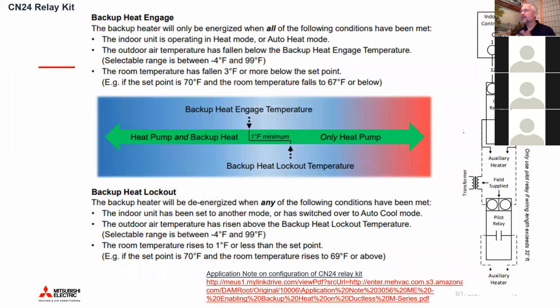Okay, great. And so just taking a little bit closer look at how, on the wall mount units or the units that have remote controls, you would set this up. This doesn't apply to the ducted systems, but on the ductless units, the ceiling cassettes or the KJ or the FS wall mount unit, there's sort of a secret push-a-bunch-of-buttons sequence on the remote in order to adjust and set up the CN24 relay capabilities. All the capabilities are already built into the ducted units and the P series, and so you can configure them separately. They already have some of those basics. They would turn on right out of the box. You can adjust the settings, but they have defaults. With the KJ and the FS, you have to initiate it using the IR remote control in order to set it up.